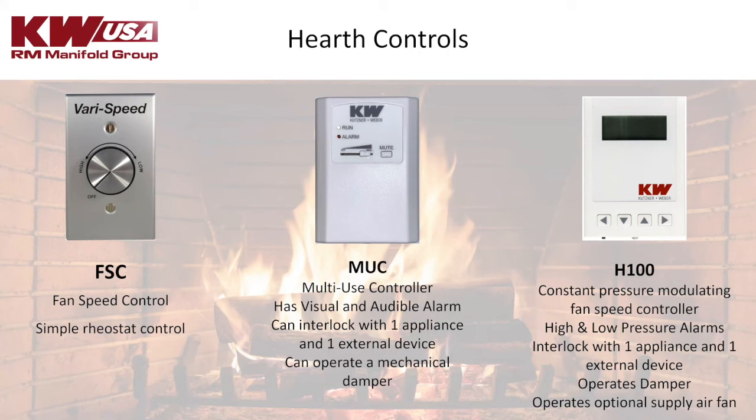And then we also offer an H100, which is our premium hearth controller. It's a constant speed pressure modulating fan speed controller that automatically adjusts that fan speed to maintain a constant negative pressure, whatever you set your set point at in that system as that draft is changing. So it works with a bidirectional pressure transducer. It actually senses the pressure anywhere between positive 1 inch and negative 1 inch.